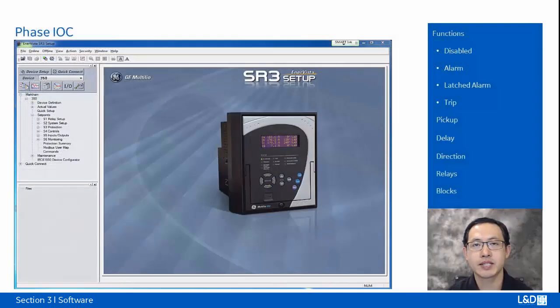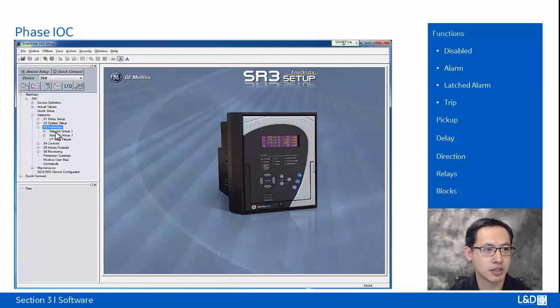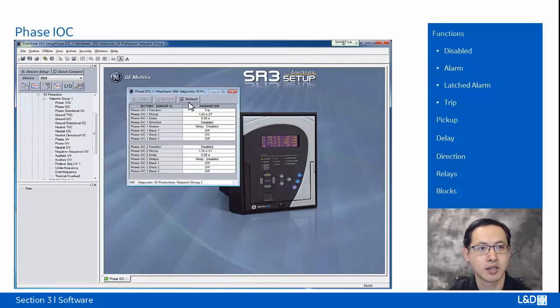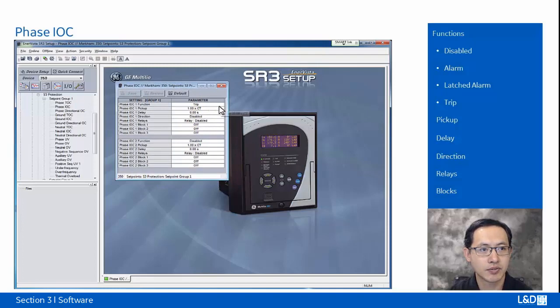Next, we'll use Phase IOC as an example to show some common set points. To access Phase IOC, we can go to Set Points, Protection S3, and Set Point Group 1, then click Phase IOC. The first setting for the Phase IOC 1 is the function. On the function, we can choose Disable, Alarm, Latched Alarm, and Trip. If the function is set to Disable, it means this feature is not operational.